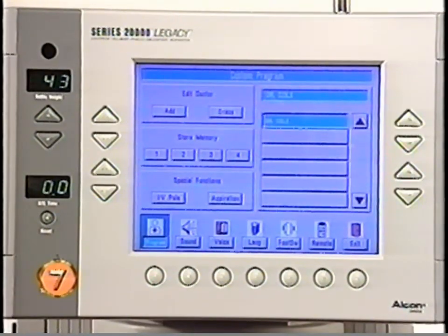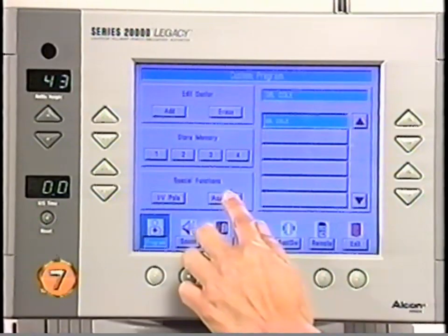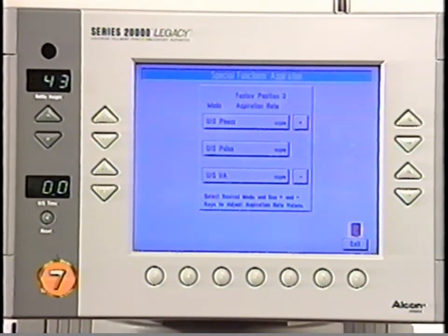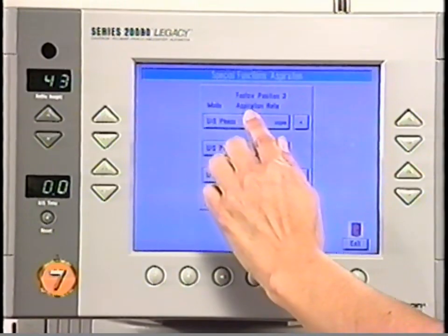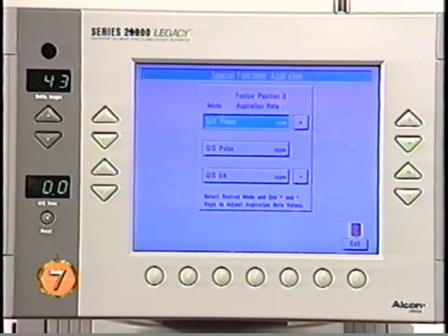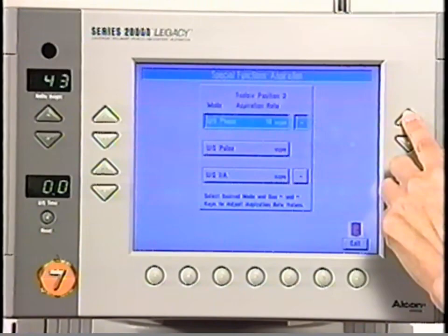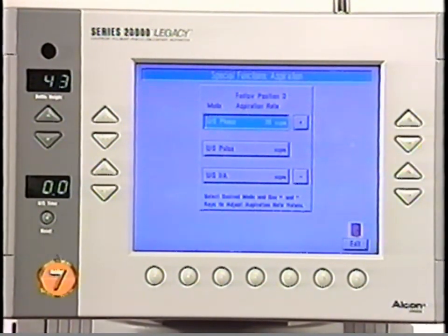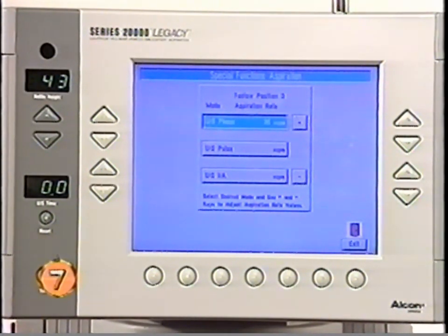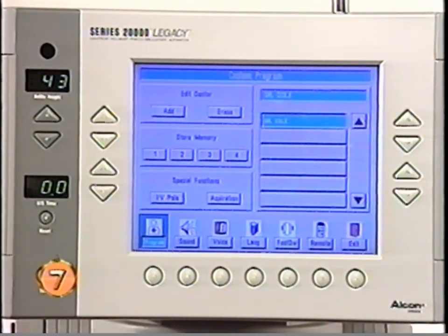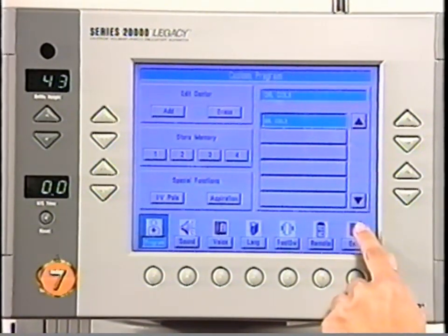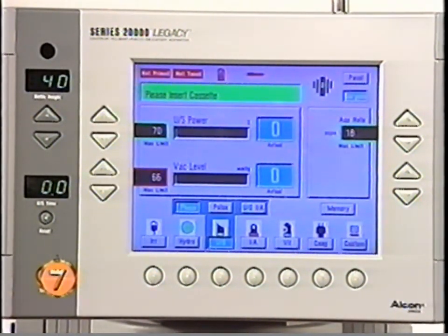To customize aspiration flow rates in the ultrasound modes, press the aspiration button in the Special Functions box. Different aspiration rates may be programmed for foot switch positions 2 and 3, but the foot switch must be depressed in position 2 or 3 before the screen will display the flow. Program flow rates using the same procedures as for IV pole programming. Press one of the 4 store keys to save all settings. Each doctor has the option of 4 programmed memory settings in the store memory. Press Exit to return to the main menu.